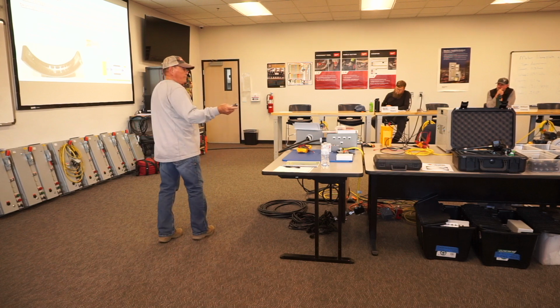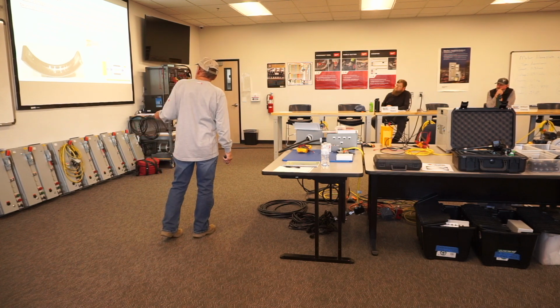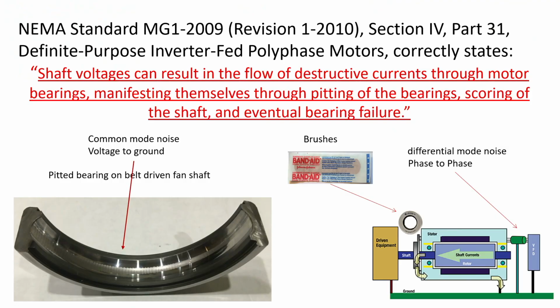So here's that bearing that just passed around. Common mode noise. Common mode is voltage ground, voltage neutral, voltage ground, because you don't have a neutral for the most part in the motor. So you said right there, if you bonded it, but you didn't ground it, you didn't really do anything? What if you grounded it, but didn't really bond it? Would it be the same result?